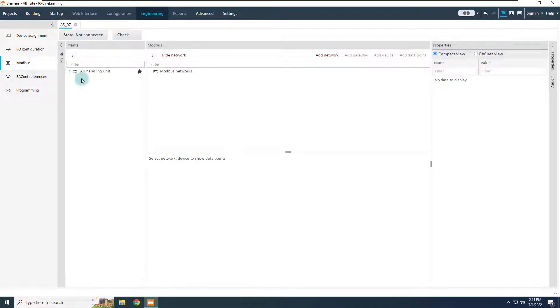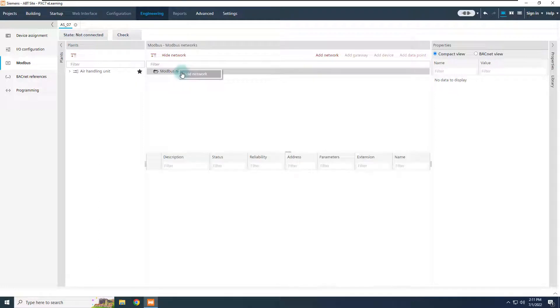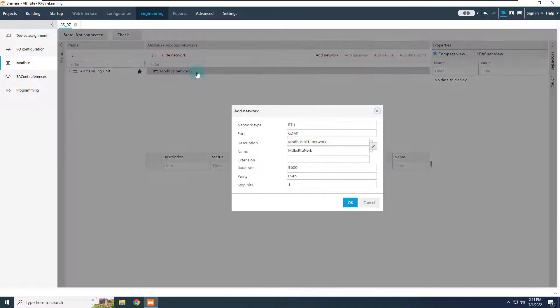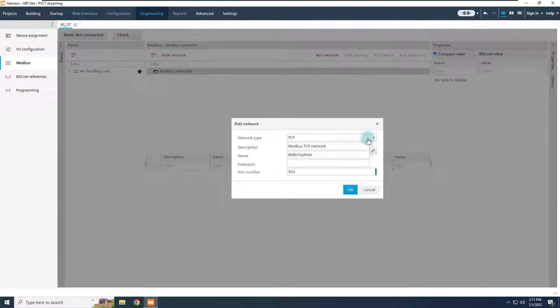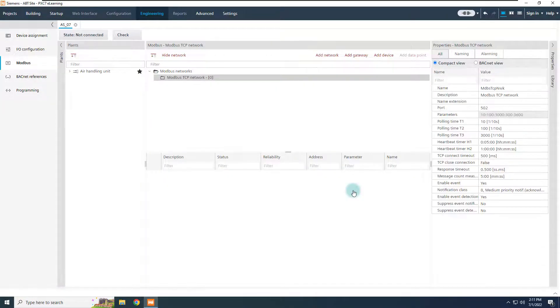Right click to the root node and add a new network, or simply use the commands on the right side corner. Switch the network type to TCP, and keep the port number as default 502, as this is the port used by the gateway in our example. Of course, this depends from the gateway itself, please follow the instructions from the vendor.